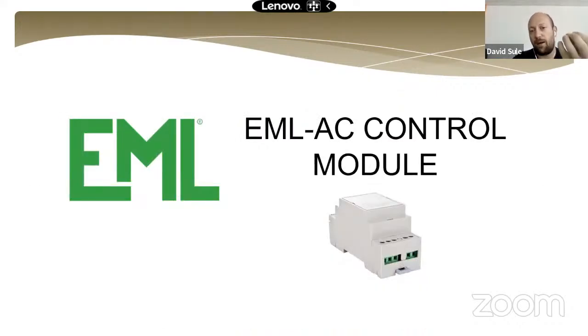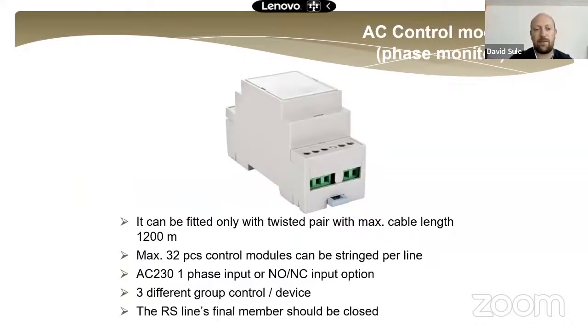I talked a lot about the EML AC control sub-dB monitoring module. So this section will be the end of the presentation, and I will close the presentation with this AC control module. This module is connected to each other with an RS485 network cable. This network cable can be 1.2 kilometers in length, and a maximum of 32 pieces of this control module can connect into one panel. Every panel can control 32 control modules, and any control module information can be sent to other panels. So no need to connect every floor sub-dB to every panel.